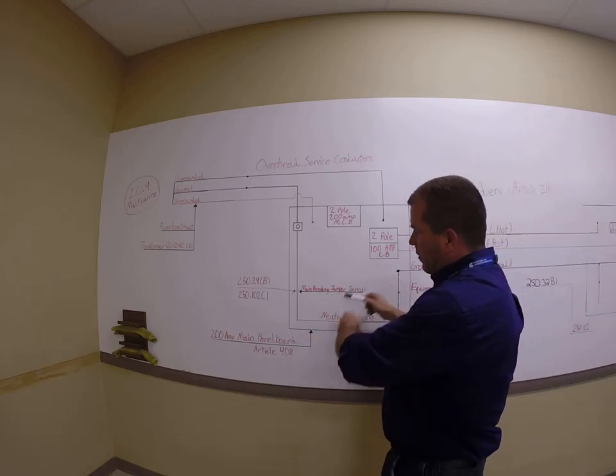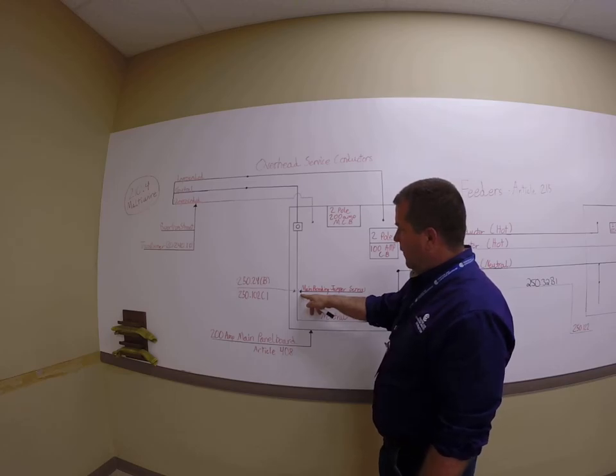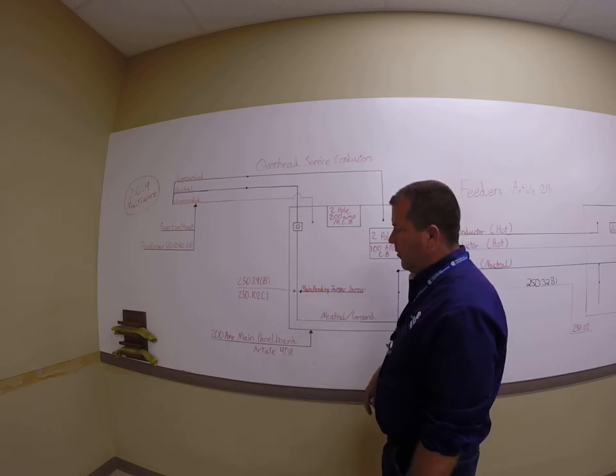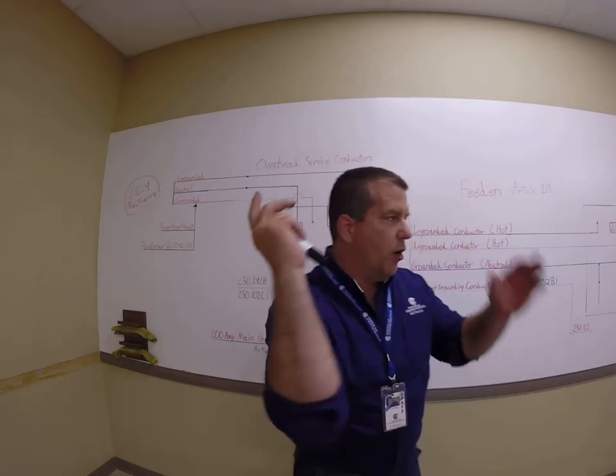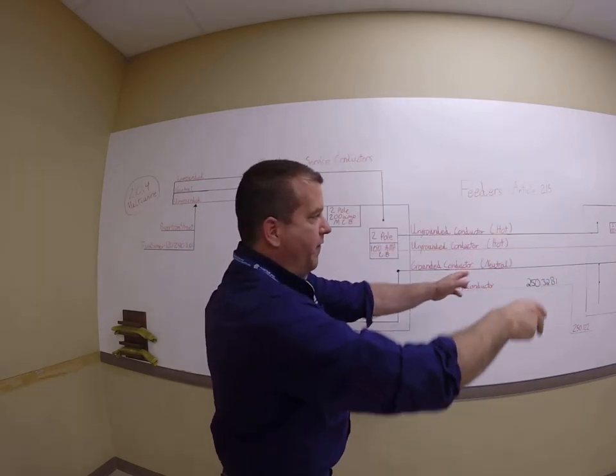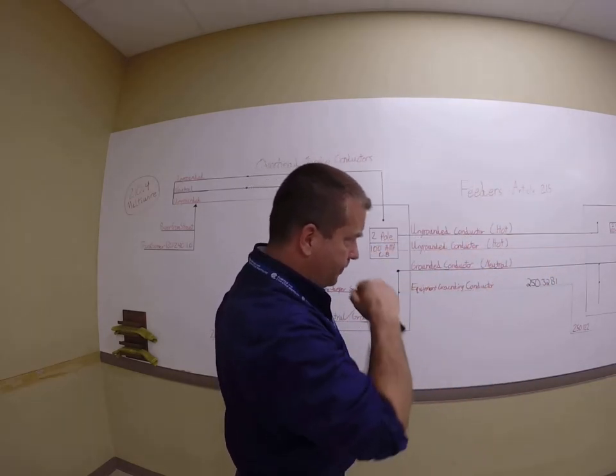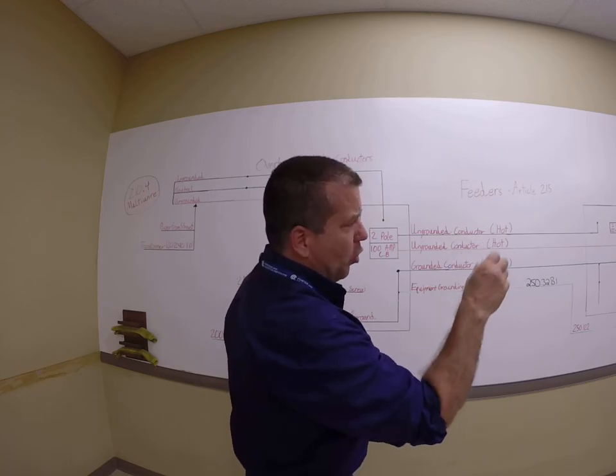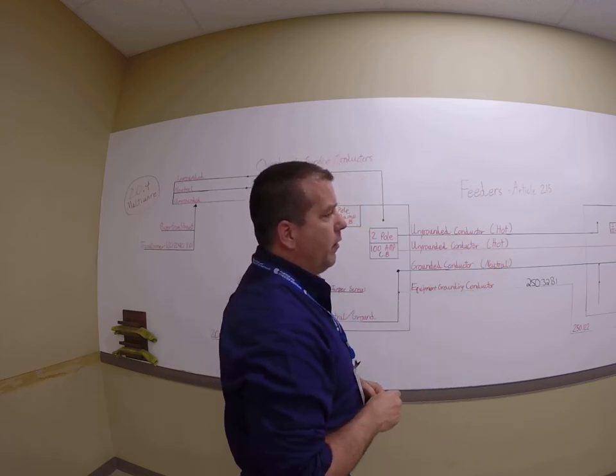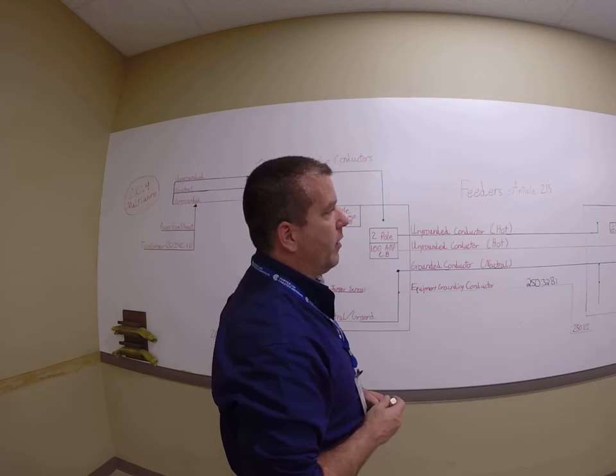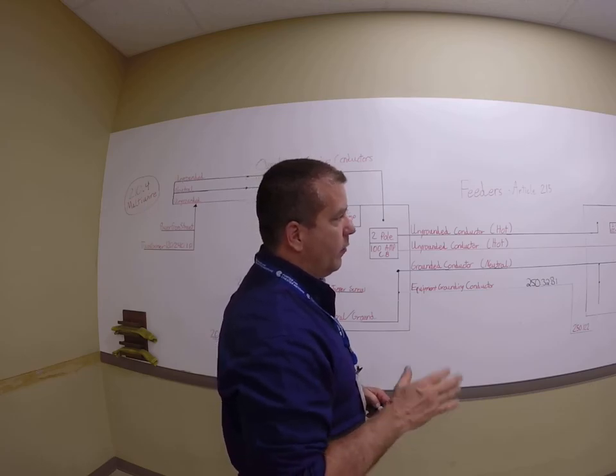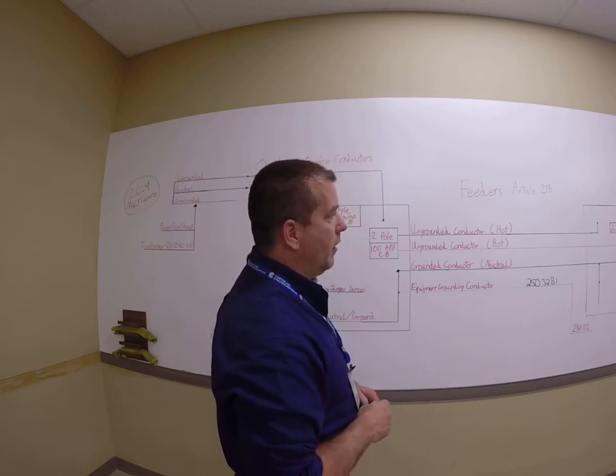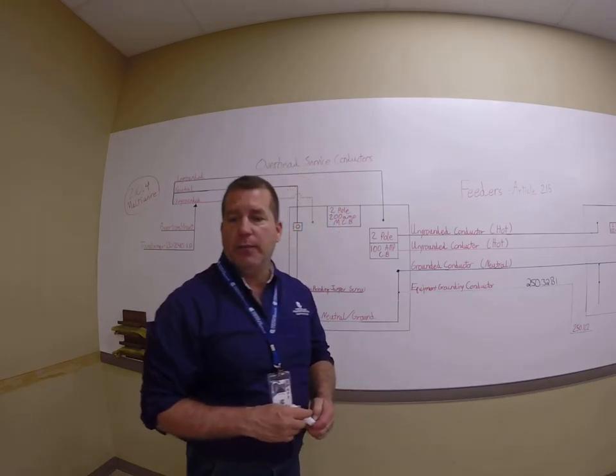Main service, first form of service disconnect, main bonding jumper. Any panel that's off of that, away from this, becomes a sub-panel. Therefore, no main bonding jumper, screw, strap, or any other means to connect the equipment grounding conductor to the grounded circuit conductor. We want to keep those paths isolated. Objectionable current's a real thing.